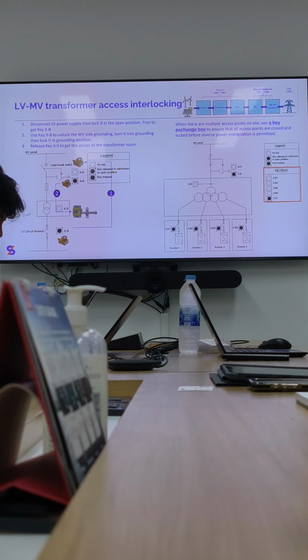This is again some example of the usage, more toward the MV and LV panels, also called upstream and downstream. So here we first isolate the LV side, isolate the breakers, and then lock it. The key goes up to here, to XB to XB.